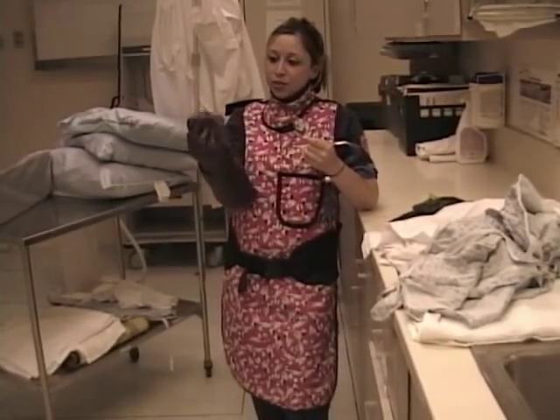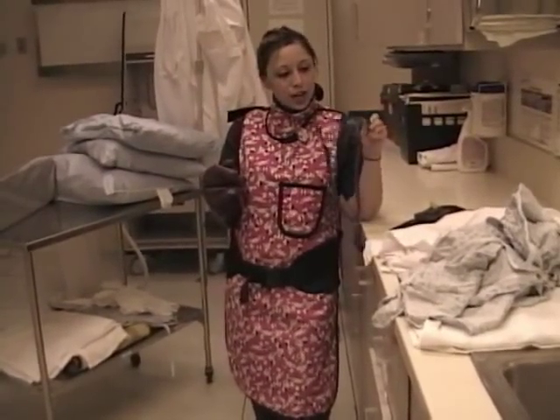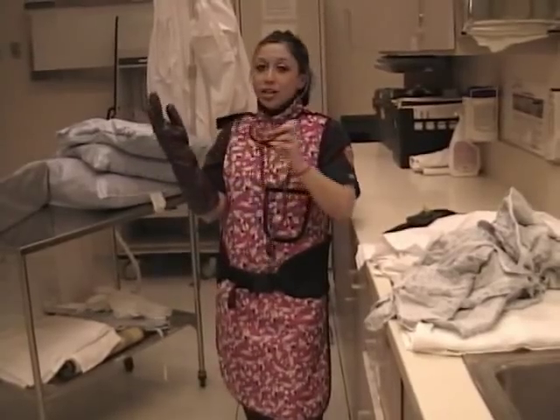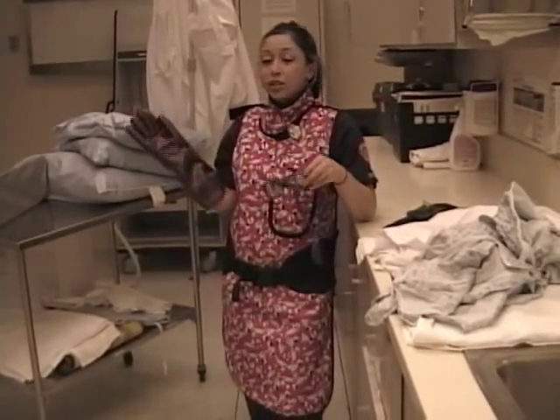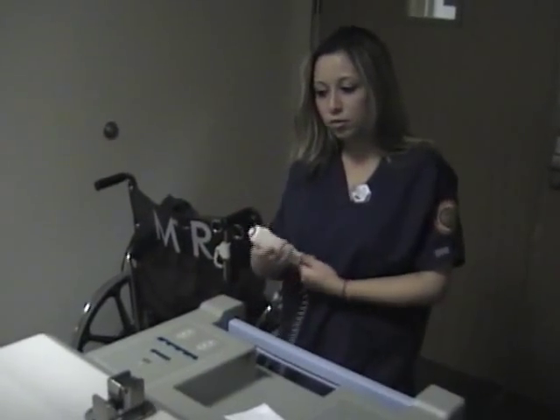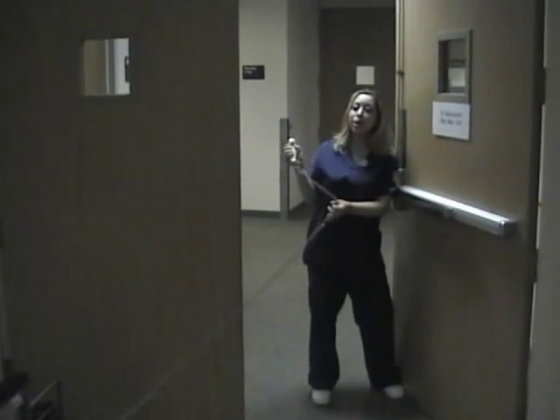The lead gloves are pretty heavy duty, but once you get used to wearing them and you know you're protecting yourself, you wear them. There are also these glasses — so if you have to be in the primary beam and your eyes aren't covered and you're pretty close to it, you can always wear these. They even have the side lead shield, so these are pretty handy. Before an x-ray, you want to make sure you get the maximum distance possible away from the patient, and always alert the personnel near you before you shoot. Take a deep breath — X-ray!